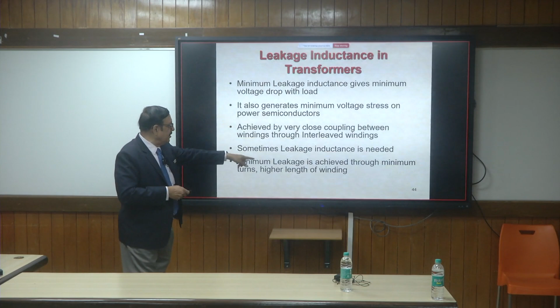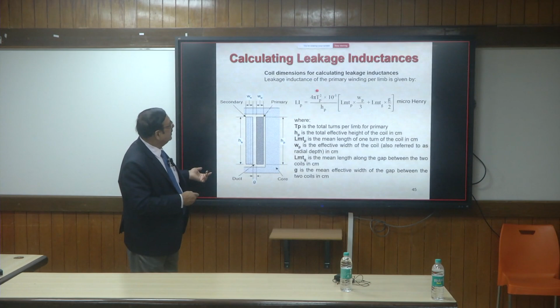Minimum leakage inductance is achieved through minimum turns and higher length of winding, something you must note if you want to reduce the leakage inductance. This is the formula for leakage inductance taken from any textbook. If you look at the formula, the height of the winding is in the denominator. So if you make the height bigger, your leakage inductance for the same number of turns and same core area will come down. And if you have fewer turns, your leakage inductance will come down too. So if you want a transformer with low leakage inductance, change the type of core to get such benefits. It's not necessary that the core you're using has to be the best.